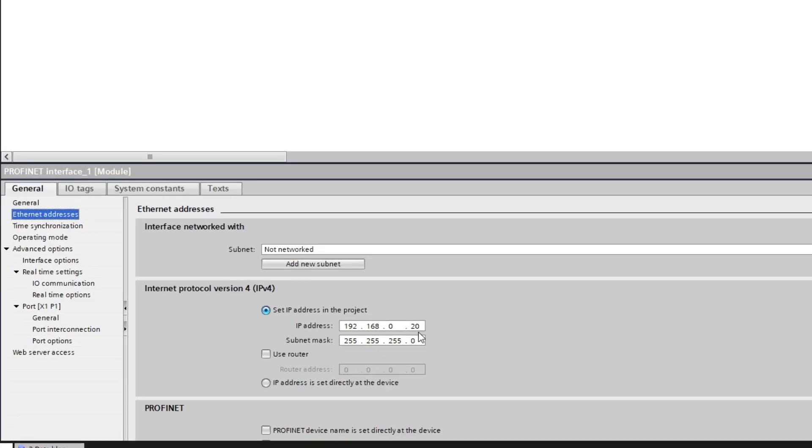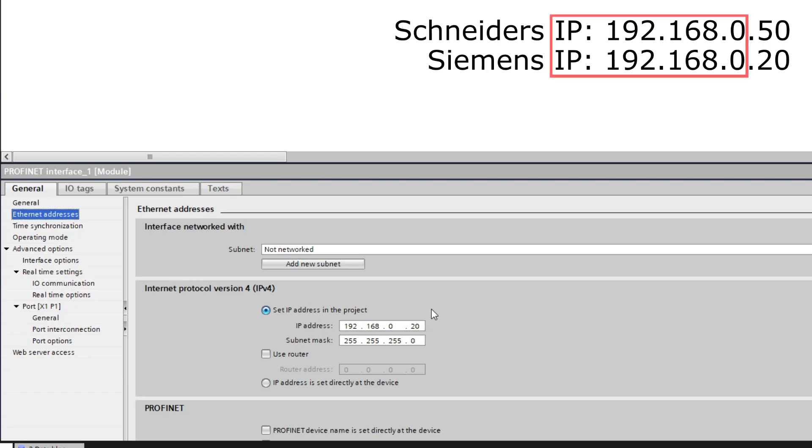In TIA Portal I already made a project with my PLC added to the devices and networks view. If we click on the PLC's Ethernet port we can change the IP address if we want to. What's important is that the IP address is in same subnet range as the client.